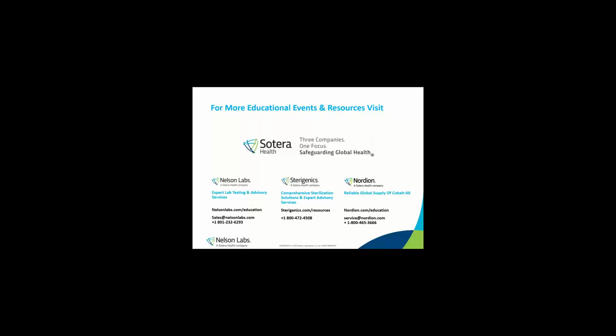Well, some of this may have to do with timing. Remember, ISO 11607 was first published in 2006, and there weren't any guidelines before then. 11607 is very specific on saying you need to address microbial barrier, but it doesn't say exactly how. If you have a really old validation, it's possible that somebody's looked at it using an older standard that wasn't specific for including this element. But there are multiple ways to do it.